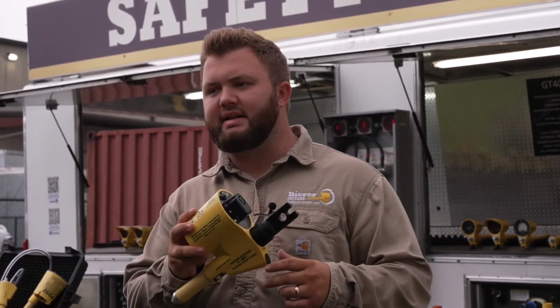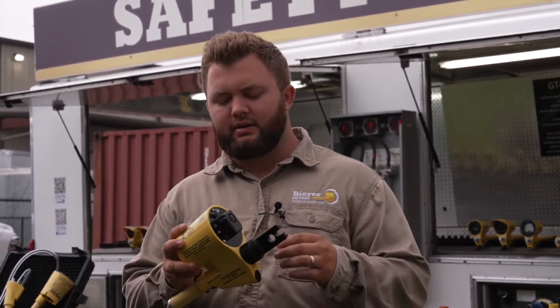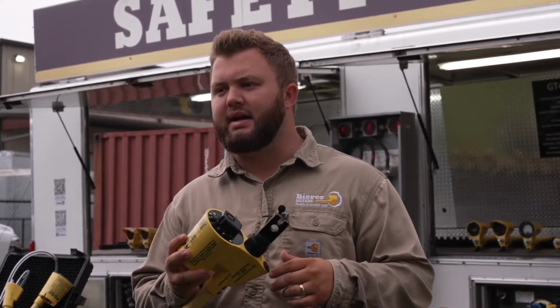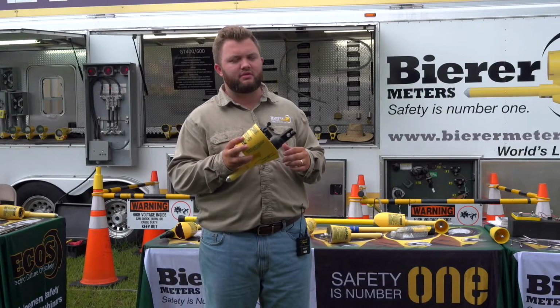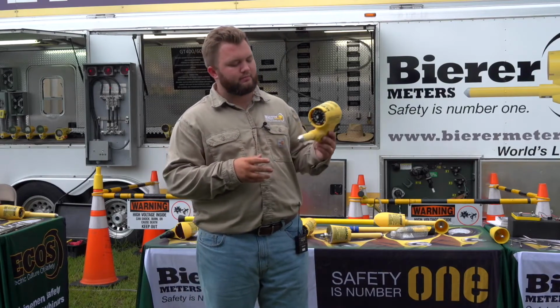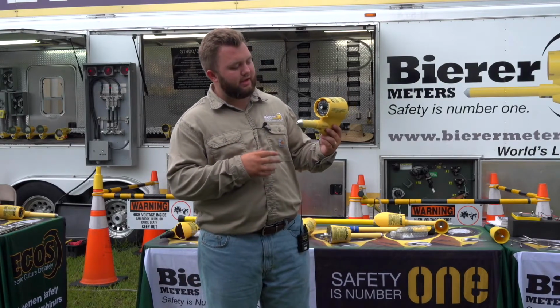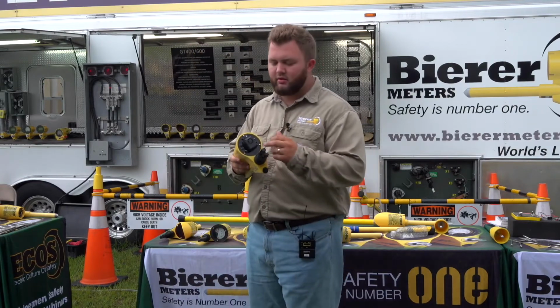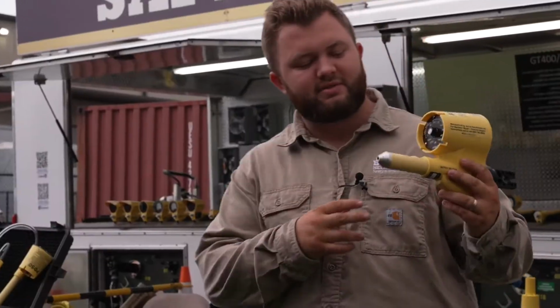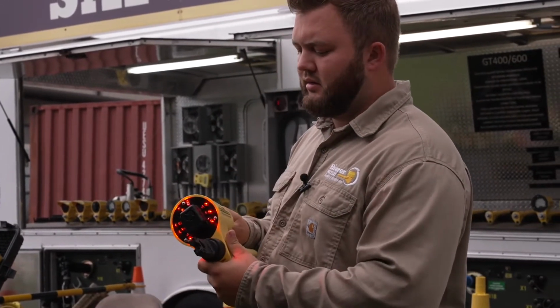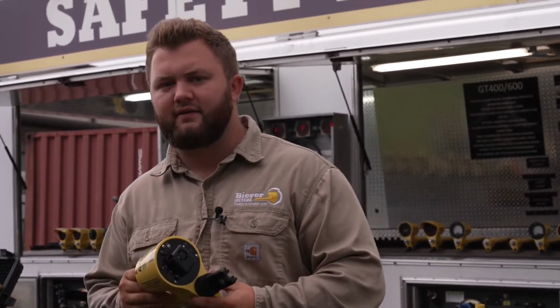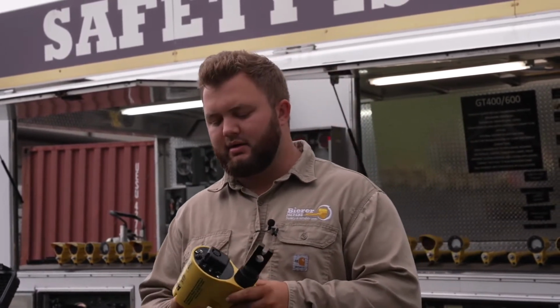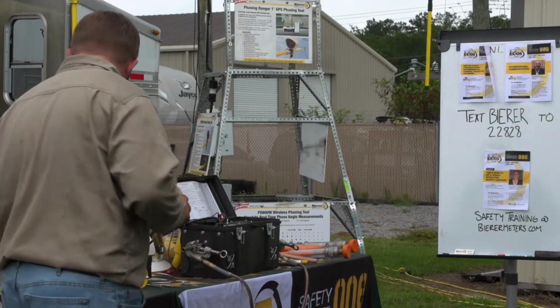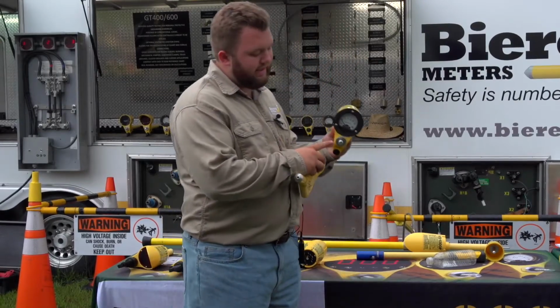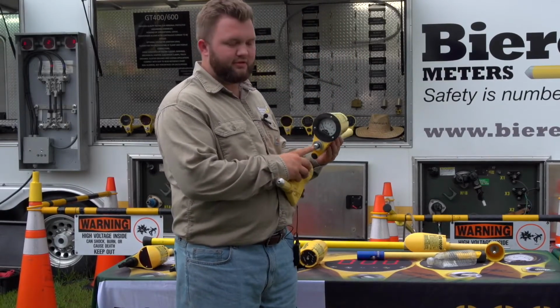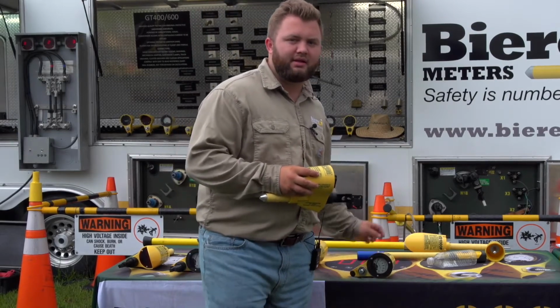But again, inside these tools, ours use a 9-volt battery. There's no transformer inside the device that's stepping that 9-volt battery up to a high voltage to give the tool a true tool test. With that 9-volt battery, on the AV meter or horn and light device, you're going to flip to the test position on the back. You want to hear the horn and see the light. If you're not hearing the horn and seeing the light, you want to get a good battery in the device. All of our tools house the 9-volt battery behind the Liveline tool fitting on the front. So just unscrew it and get a good, known working 9-volt battery in the device.